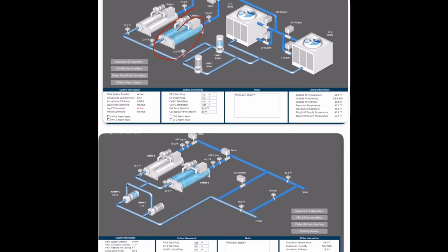So here we got our condenser, we got our pump over here, and two cooling towers. Like I said, the only difference in this one is that we're gonna use water to subcool our refrigerant instead of air. In this case, chiller 2 is running and pump 1 is running and two cooling towers are running. Our water flow is gonna go through this line from the condenser, which is gonna be full of water. Let me explain to you exactly how it is. So let me do it better.